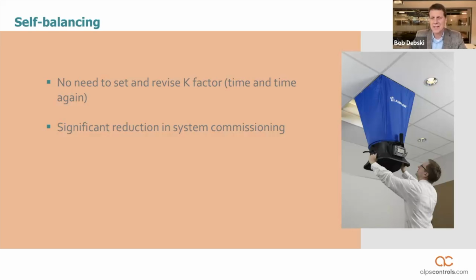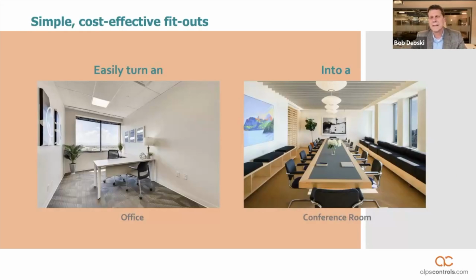There's no changing and rechanging the K factor. It accurately measures airflow immediately out of the box. So what happens? It eliminates that balancing, that time in commissioning, and additional energy savings or cost savings can be achieved. So one of the things that has plagued VAV boxes is doing tenant retrofits, especially in commercial office buildings.